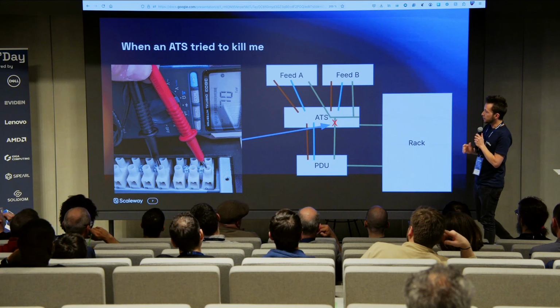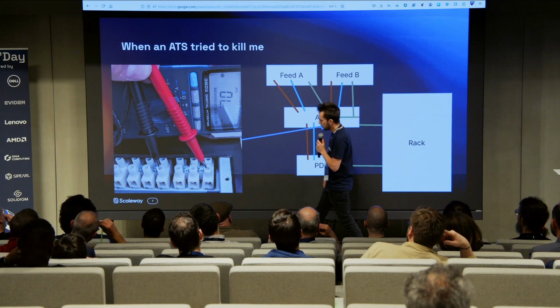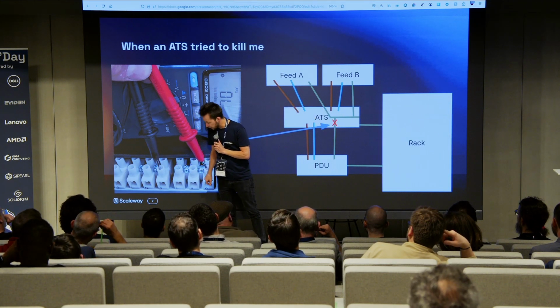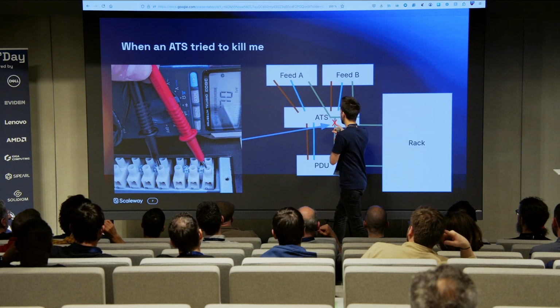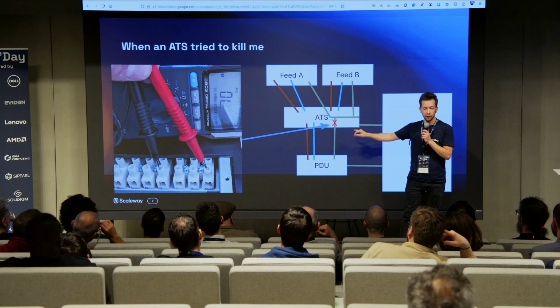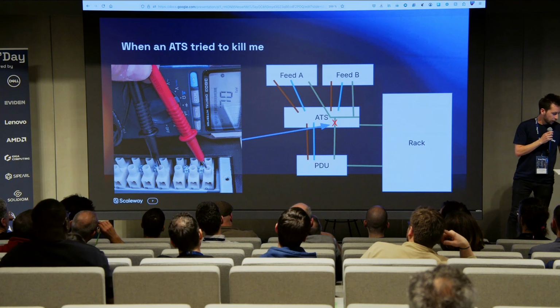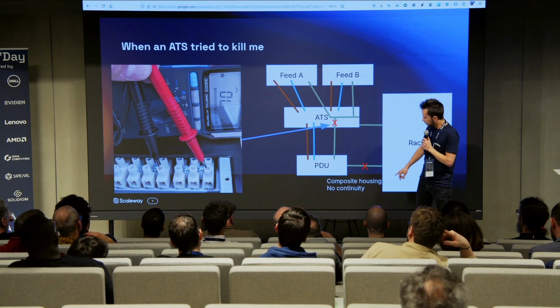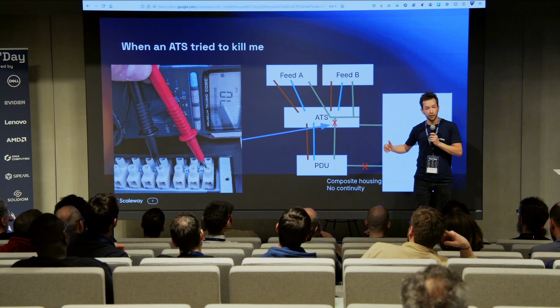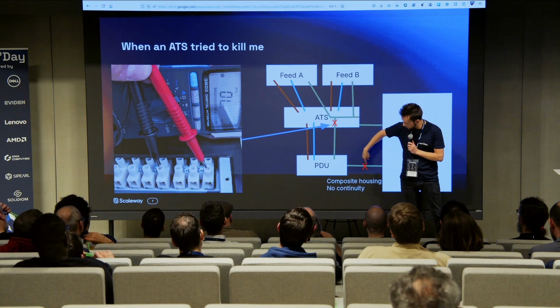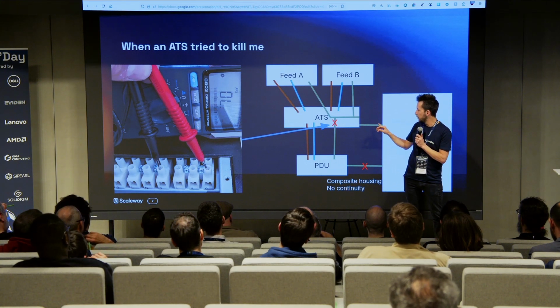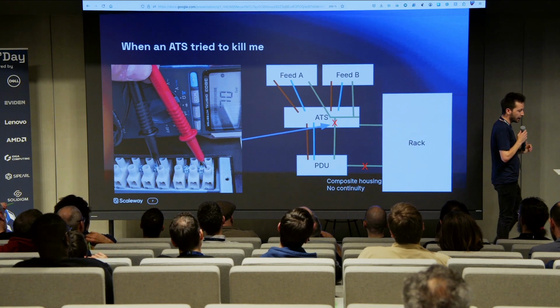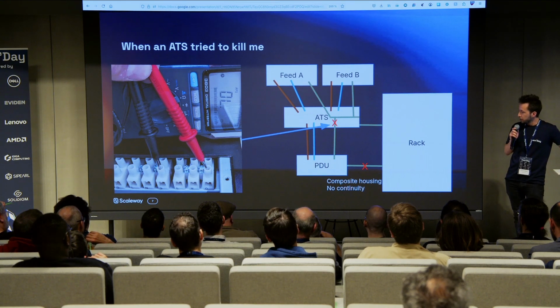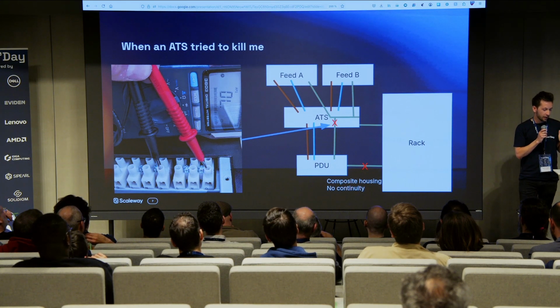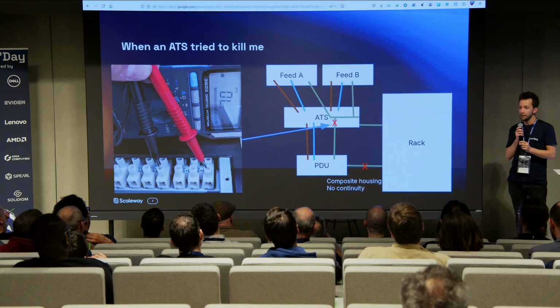The main issue was on this terminal block, where those two grounds were not connected. So this connection does not exist. This PDU is made of composites, so there is no connection here as well, not like here. So you have a PDU, a metallic mass, not grounded, so you have a ground isolated from the rest.